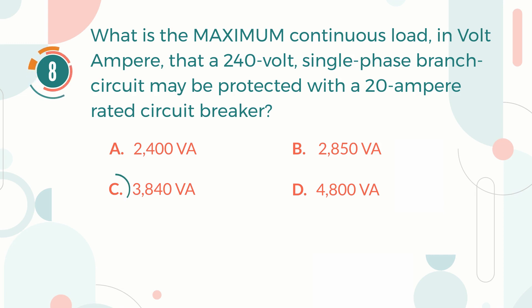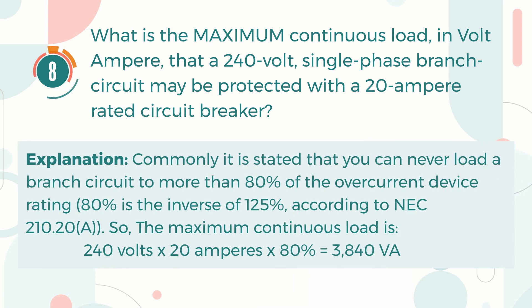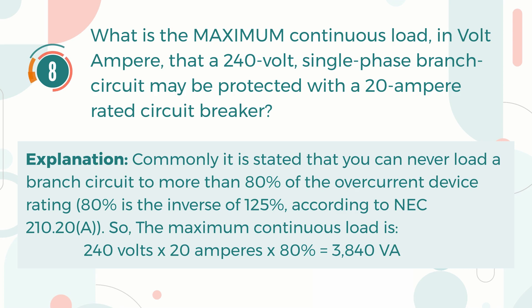The correct answer is C. 3,840 volt-amperes. Explanation: Commonly, a branch circuit cannot be loaded to more than 80% of the overcurrent device rating — 80% being the inverse of 125% according to NEC 210.20A. So the maximum continuous load is: 240 volts multiplied by 20 amperes, then multiplied by 80%, equals 3,840 volt-amperes.